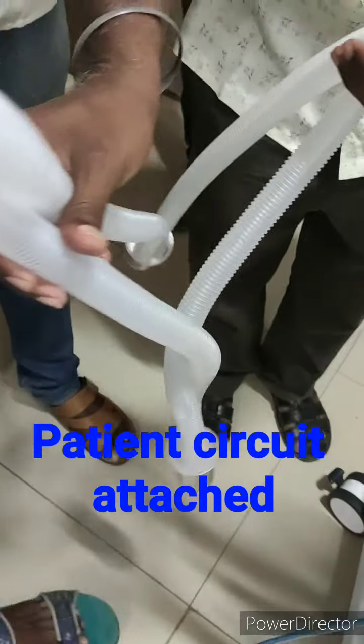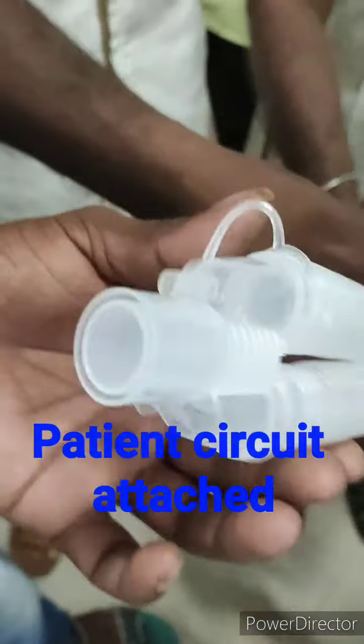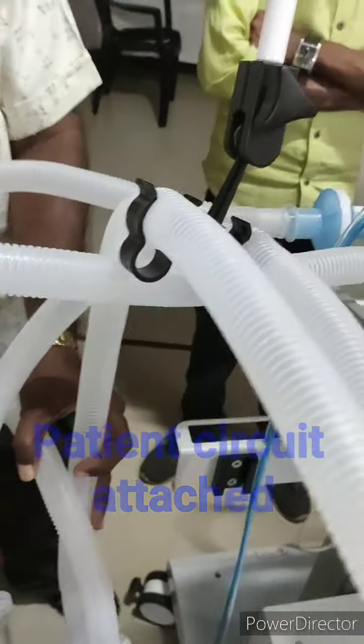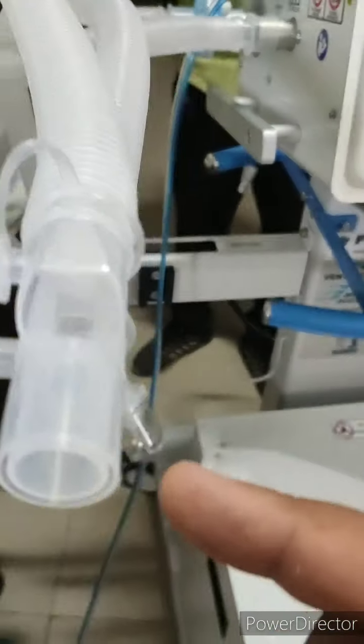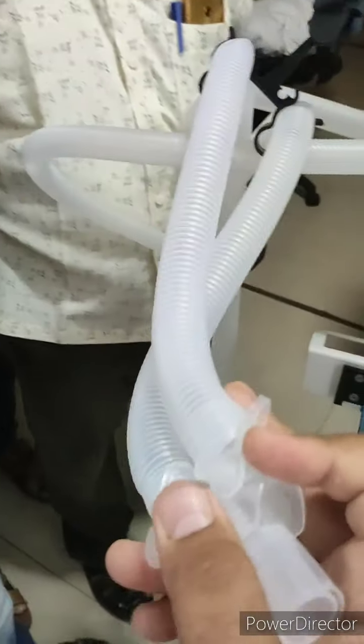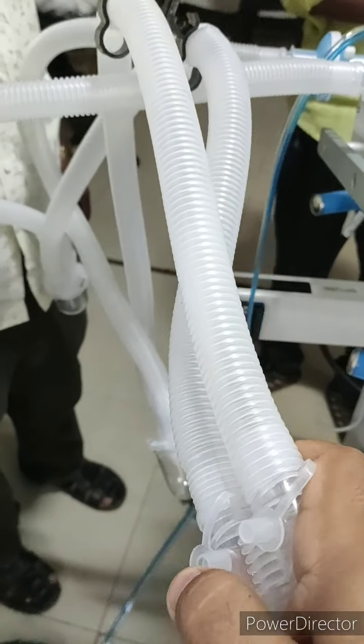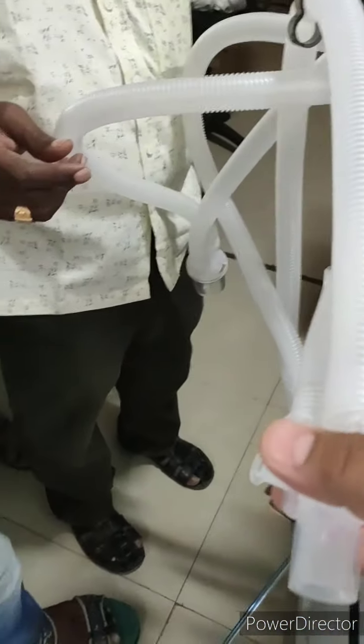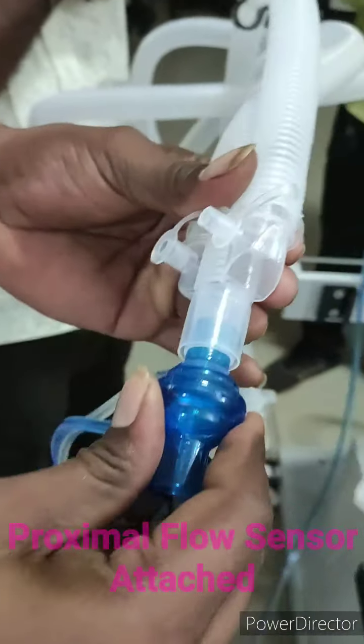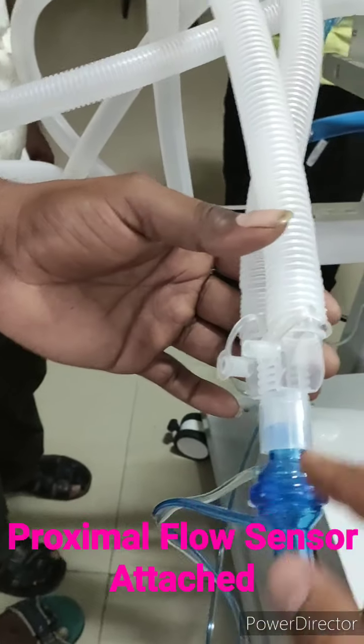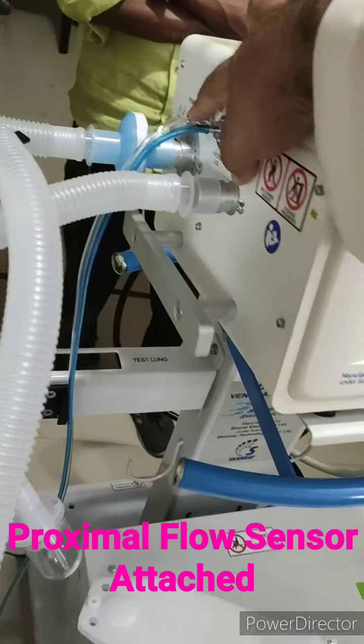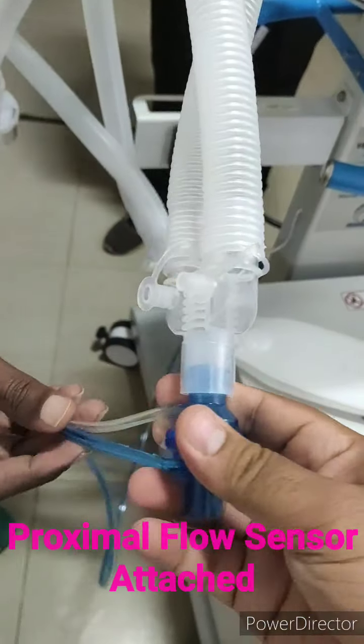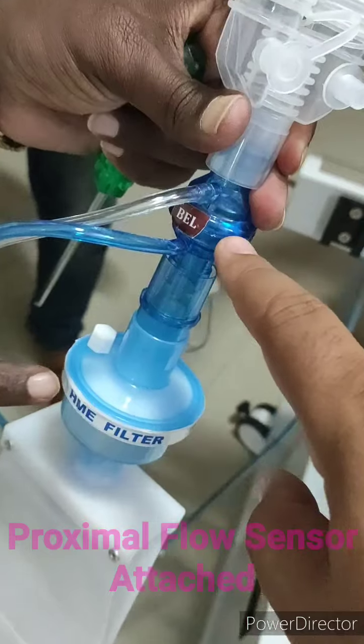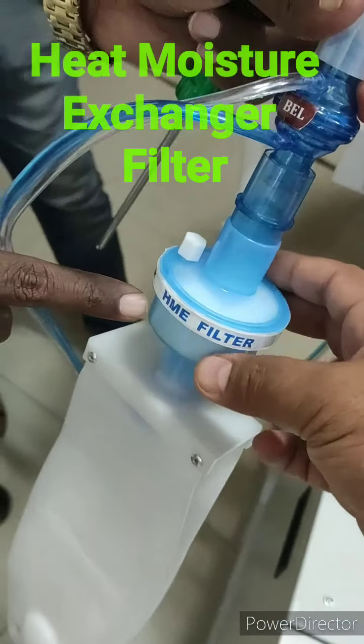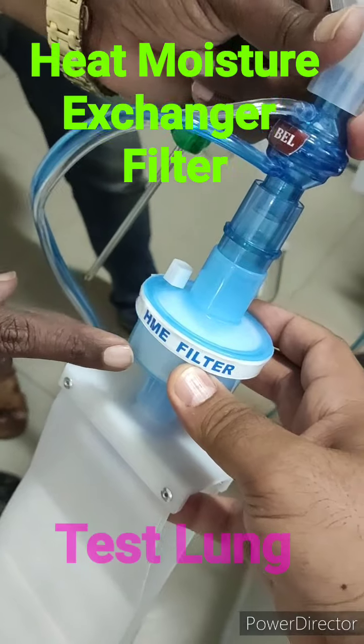Now let us look at the patient end. This is the disposable circuit, and this is the patient end. Okay, we have to make sure that these two are blocked, and while attaching a flow sensor, we should make sure that white is first, then blue. Similarly, white and then blue is the proximal flow sensor. This is HME filter, heat moisture exchanger, and this is a test lung.